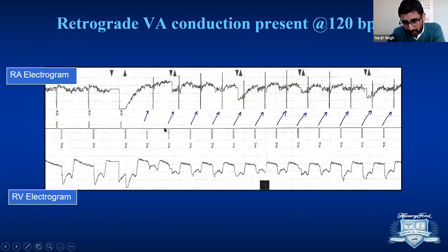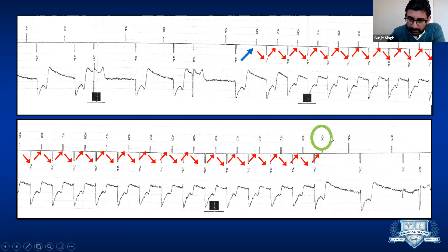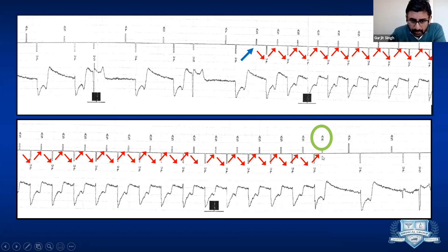So shown here is that ventricular pacing spike is going back up the atrium, and that atrial signal is being sensed, and then the cycle starts. Okay, so shown here again, usually it starts with the PVC. And then this cycle goes on where you V-pace, A-sense, V-pace, A-sense until one of the atrial signals falls into the refractory period, okay? So that can happen spontaneously and that will terminate the tachycardia, or a PMT algorithm will work. So what the PMT algorithm usually does is it prolongs your PVARP for a certain duration of time, to see if the atrial signal falls into the refractory period. And if it does, and the tachycardia terminates, that usually is a diagnosis of PMT, okay?